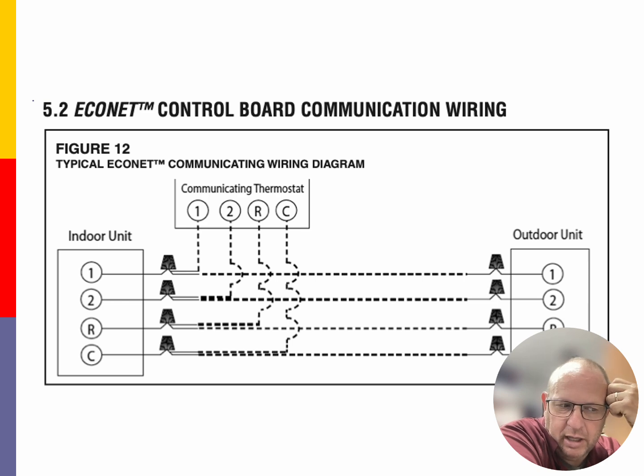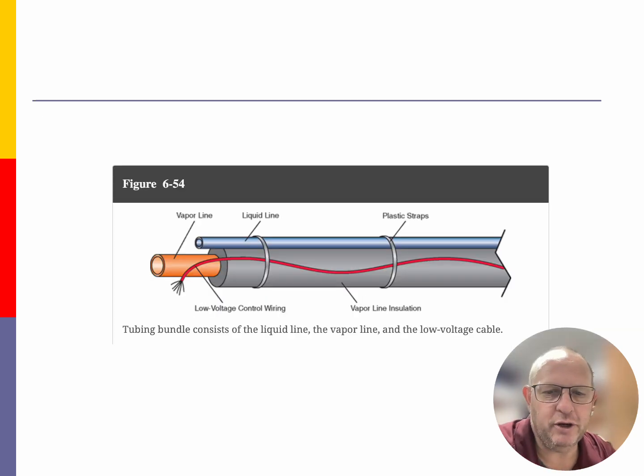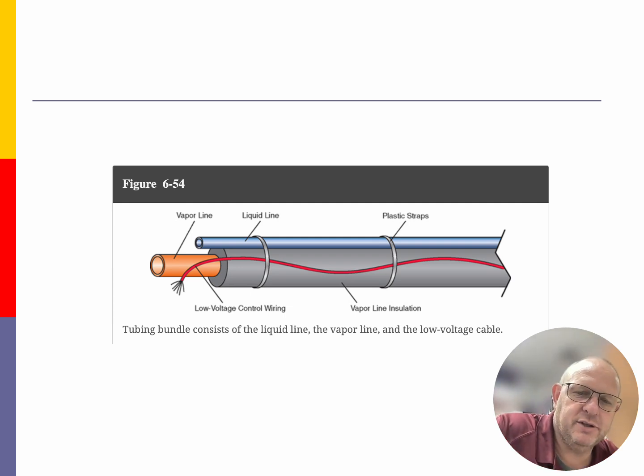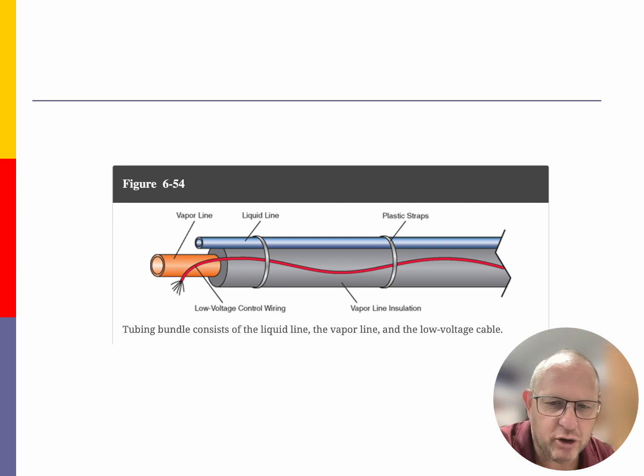So running your line sets, what I always like to do is run my liquid line and my suction line together. And these are the lines that are going to be running from the outdoor unit into the indoor unit. So our liquid line should never be touching our suction line, and you want to try to avoid at any cost any of these copper, which is a very soft metal. And if it was to touch anything that was harder than it and it was to vibrate up against it, the copper would actually deteriorate away, and we would end up with a hole in that copper.